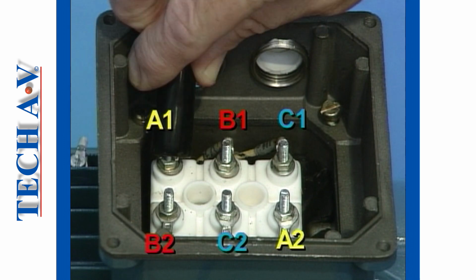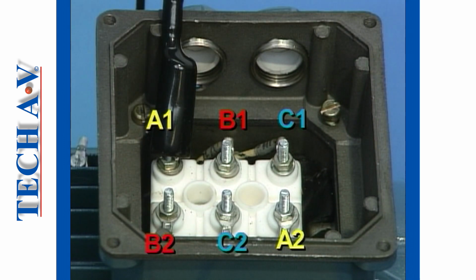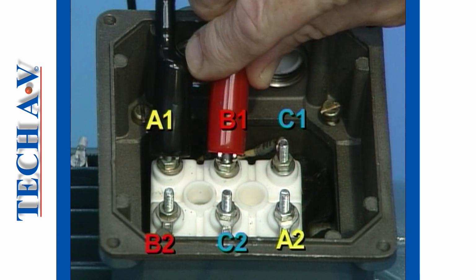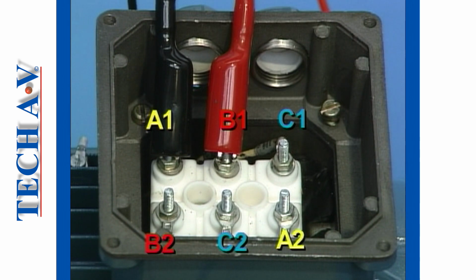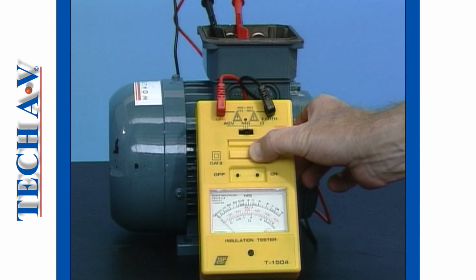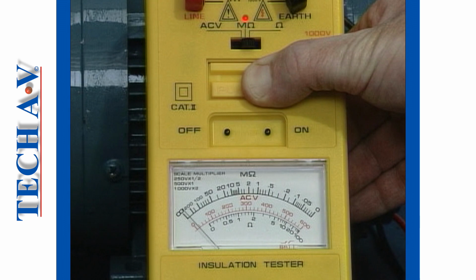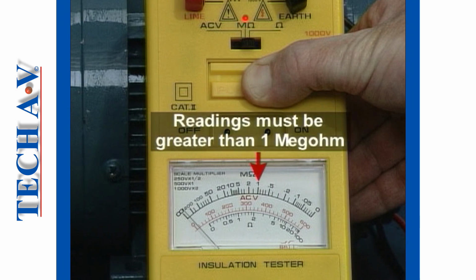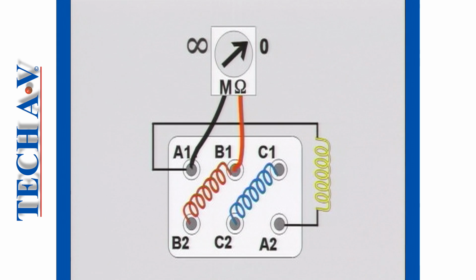Clip the test lead onto the post that we have called A1 and connect the other lead to B1. Press the test button and note the reading on the meg-ohm scale. It must read greater than 1 meg-ohm to be acceptable. A reading less than 1 meg-ohm indicates the possibility of a leakage path between the two windings.